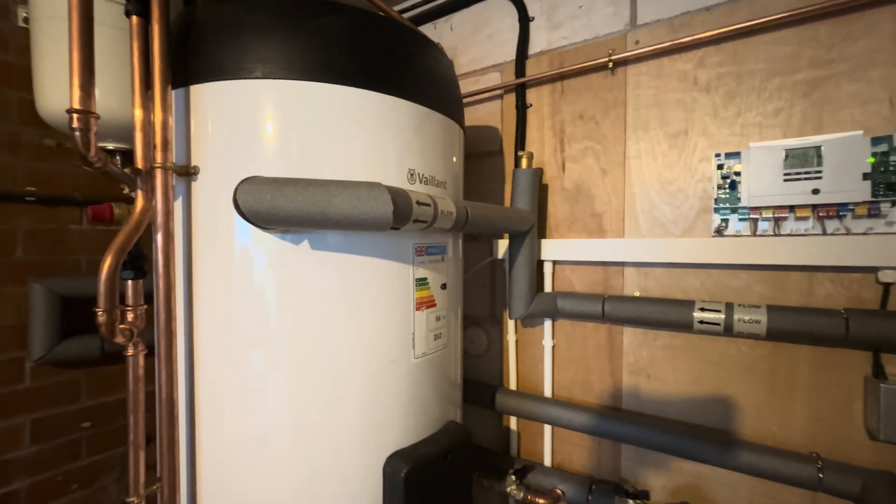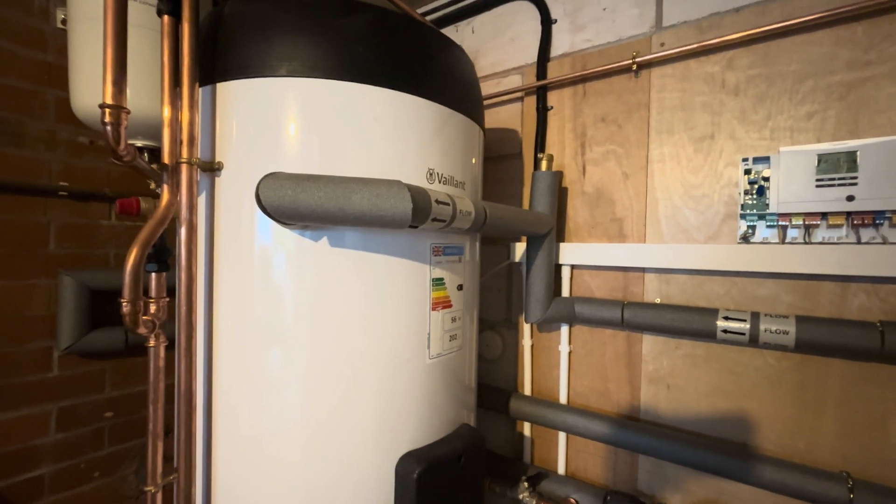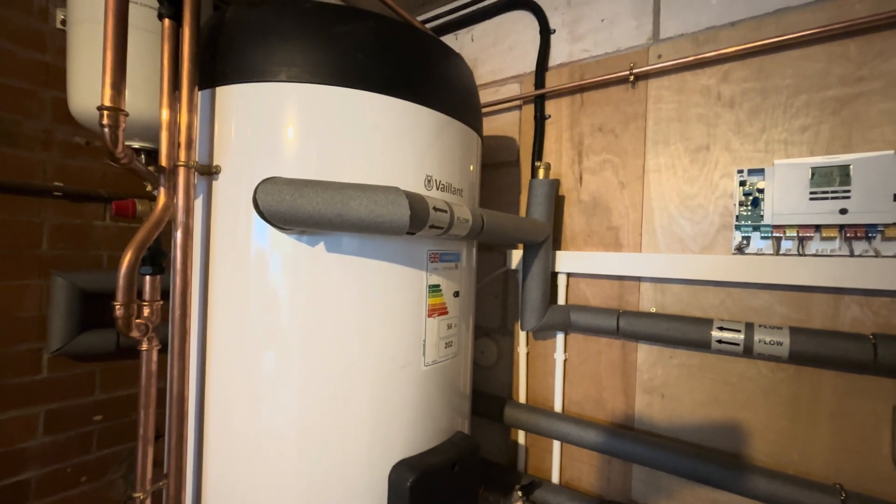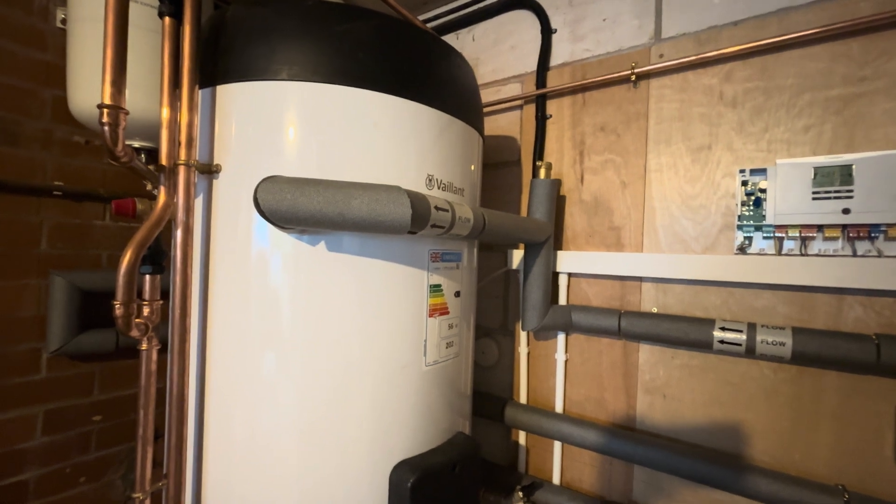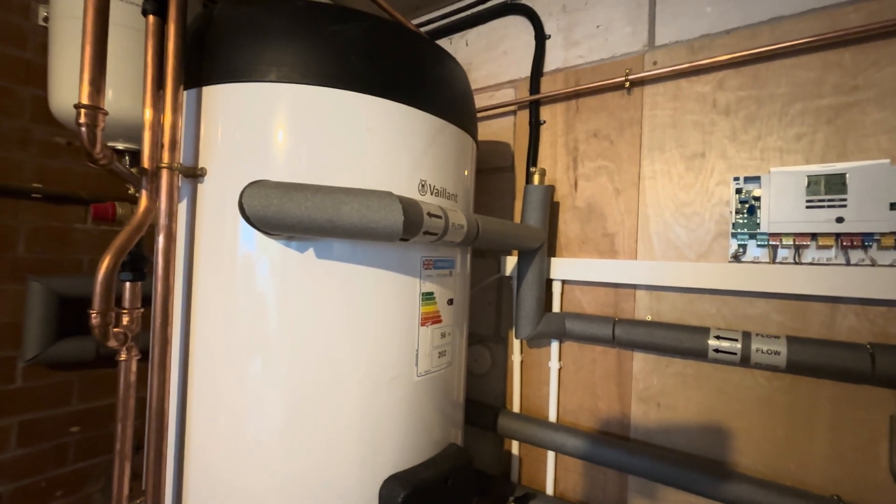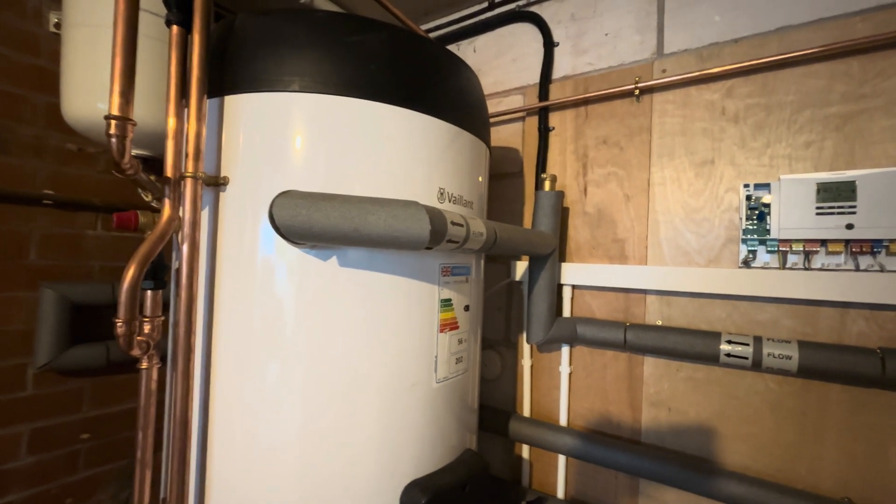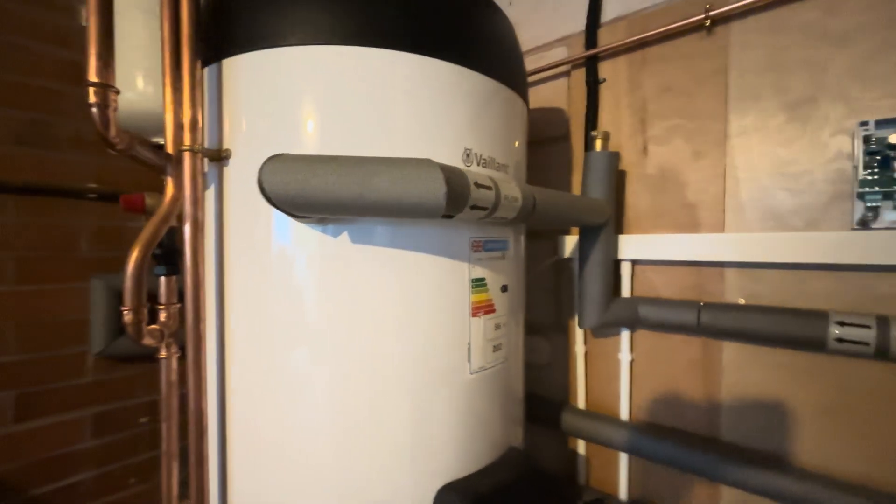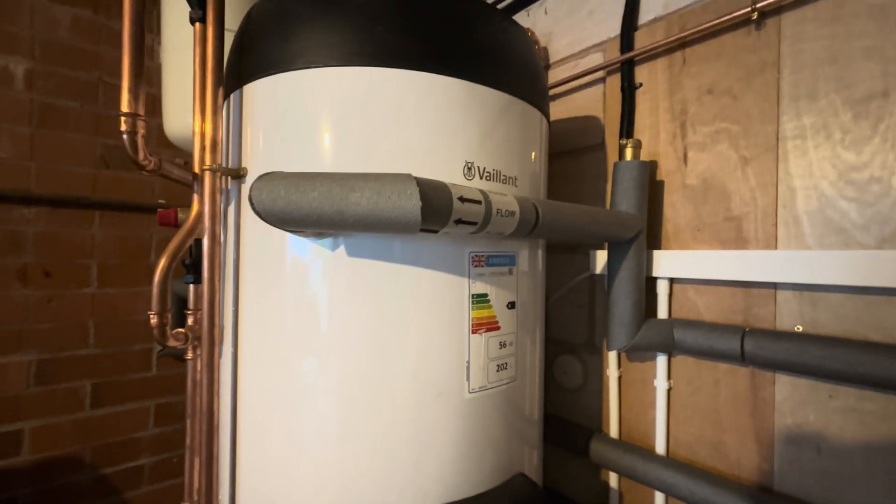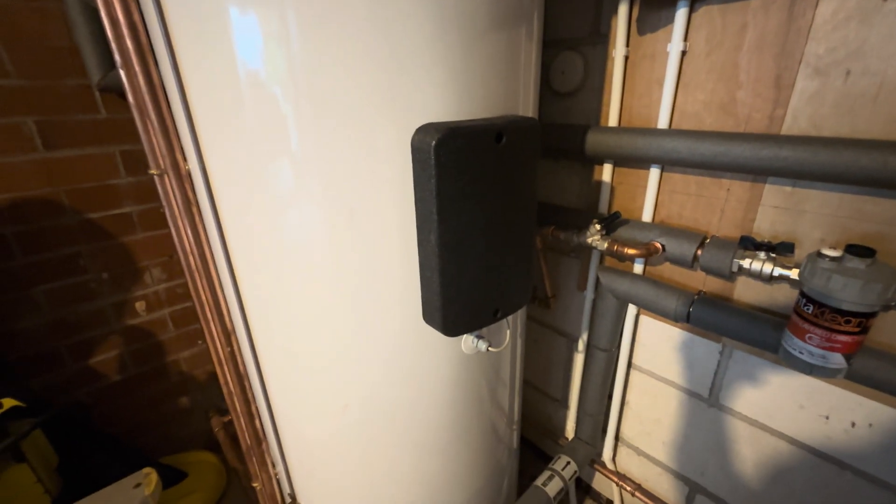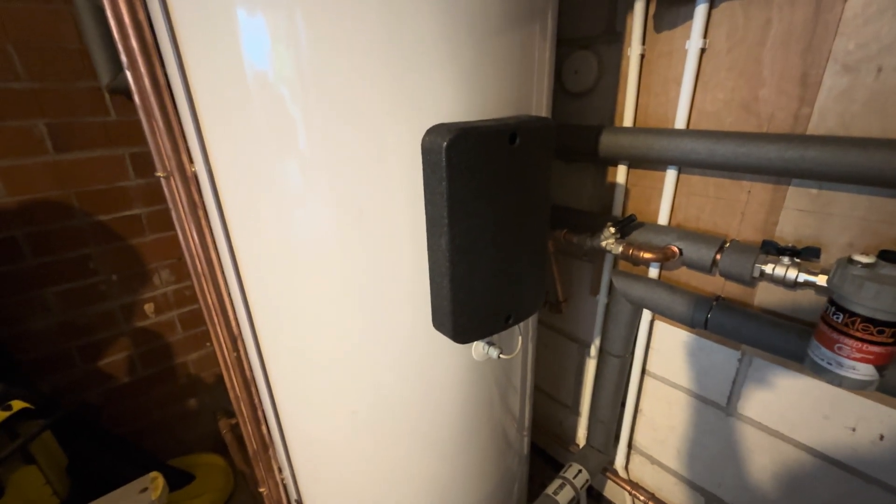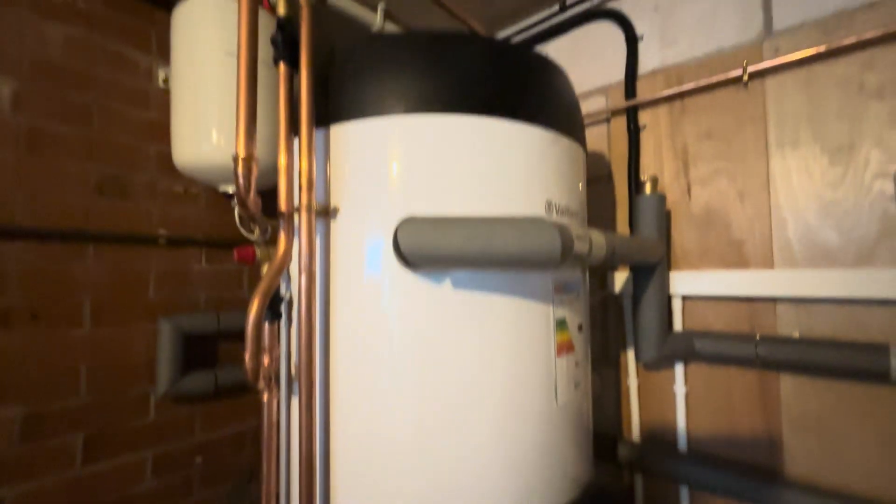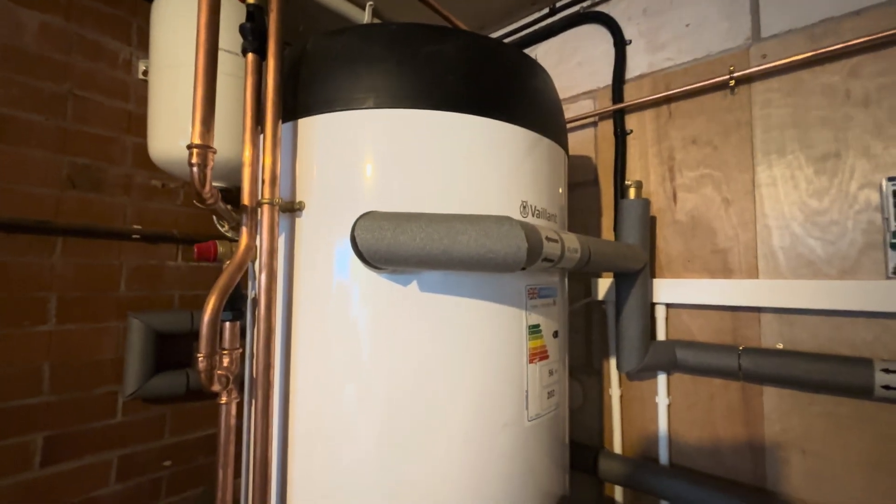So in conclusion, what we have to remember is that this was from cold. So it'll take a lot longer and use a lot more energy than the standard recharge of 45 degrees C start temperature and 50 degrees C stop temperature. This is also a 200 litre cylinder, which is a really good size. And the hot water sensor is situated about a third of the way up from the bottom, meaning everything above that sensor will be hotter than the set temperature. Hope this has been useful.